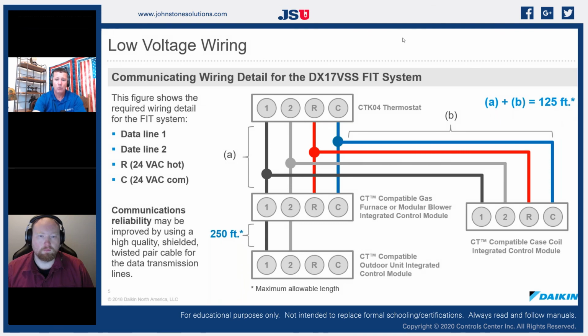If we look at why it's important to have that clean wire, if we think about what a conductor actually is, if I've got an 18 gauge wire, when we were using 24 volts AC, we had a load on the other side. We were turning on a relay or a contactor or a switch or something, right? We were energizing it. So our electrons were flowing through the center of our conductor. And electrons flow like water, so we flow through our conductor when we have a load. Well, that all changed when we went to 5 volts DC, because now we don't have much of a load. We don't have utilities that we're energizing.